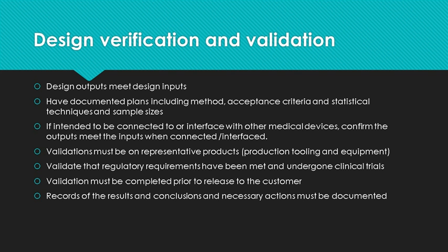If the product is intended to be connected to or interface with other medical devices, verification and validation must confirm the outputs meet the inputs when connected or interfaced with that other equipment. That's very important. That's something that has been problems in the past for some companies.